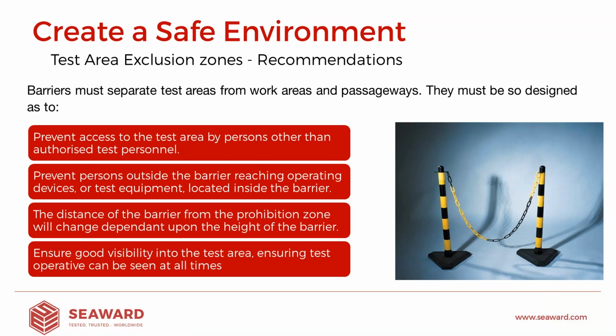So it's all very well our test operator's nice and safe, he's stood on rubber matting, but someone walking behind the test area is probably generally going to be on regular concrete flooring. What we don't want is for him to be able to reach across and touch the product under test. Now, in EN 50191, the distance away from the product will vary dependent on the height of the barrier that you do choose to use. So if it's waist height, then a human could reach a lot further than, say, if the barrier was up at around shoulder height.